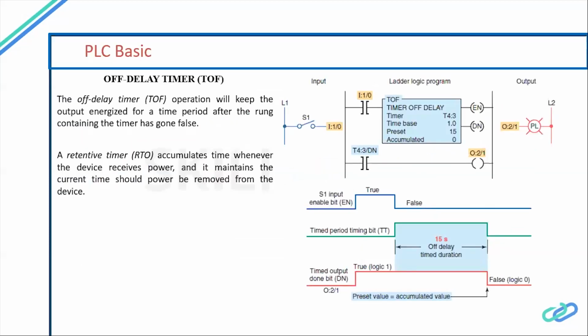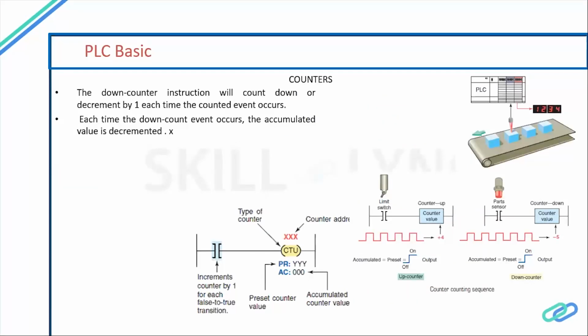The same applies to the off delay timer. Maybe some device has a malfunction. Sometimes we provide an off delay timer. We give a command so that after 5 seconds the drive should trip, not immediately. Due to this reason, we also provide off delay timers. This is a PLC based down counter. A down counter is like a production counter, where maybe 1 ton or 2 ton is added every time. Similarly, when some waste is there, we provide a down counter. Just like in a thermal plant, we use a down counter so we know how much coal we are using or how much waste there is for fly ash.